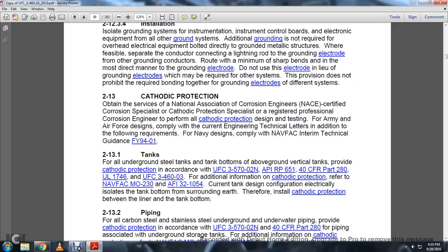213 Cathodic protection. Obtain the services of a National Association of Corrosion Engineers (NACE) certified corrosion specialist, cathodic protection specialist, or registered professional corrosion engineer to perform all cathodic protection design and testing for the Army and the Air Force. Design must comply with the current engineering technical letters and additionally with the following requirements for the Navy. Design compliant with NAVFAC Interim Technical Guidance FY 9401.